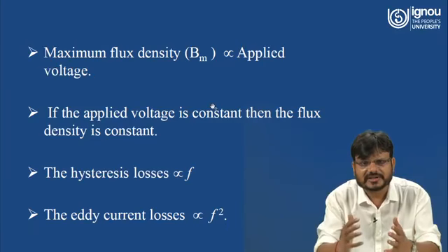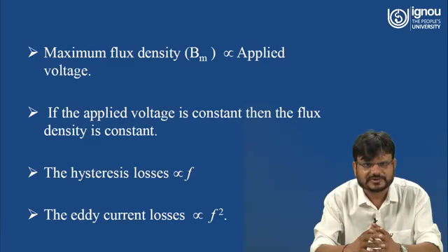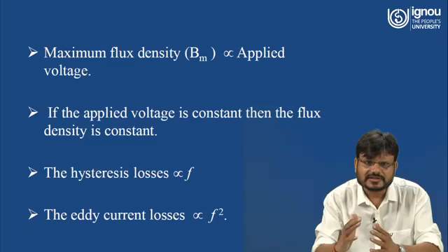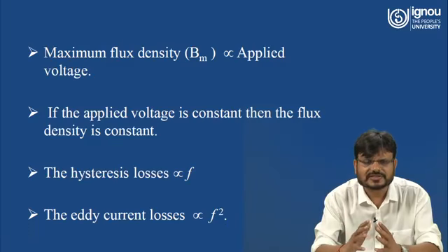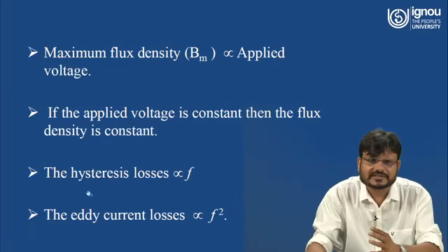At that moment the hysteresis losses are directly proportional to the supply frequency, and as the frequency changes, hysteresis losses change. Similarly, eddy current losses are directly proportional to the square of the frequency. So the variation of hysteresis losses is linear and that of eddy current losses is non-linear, and this happens only when the applied voltage is constant.